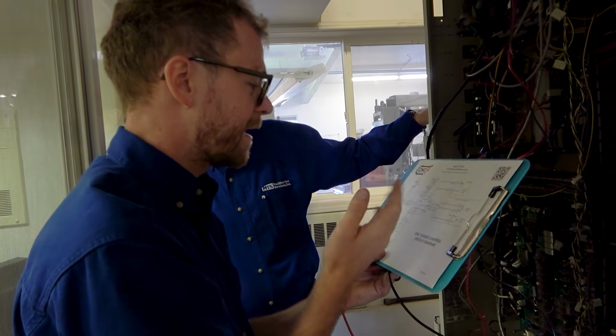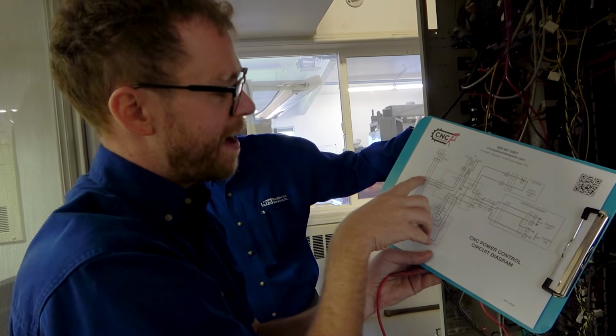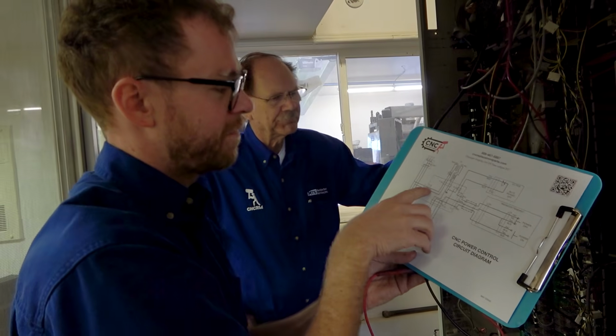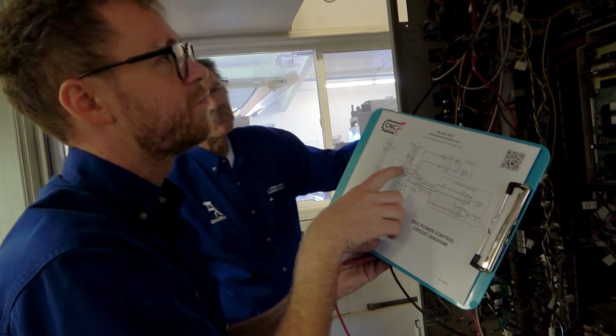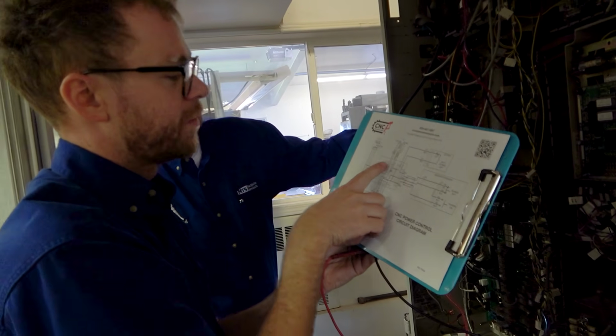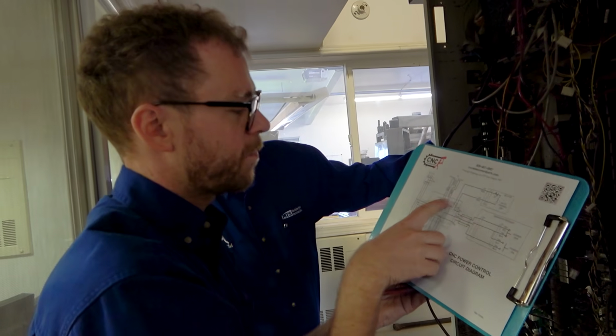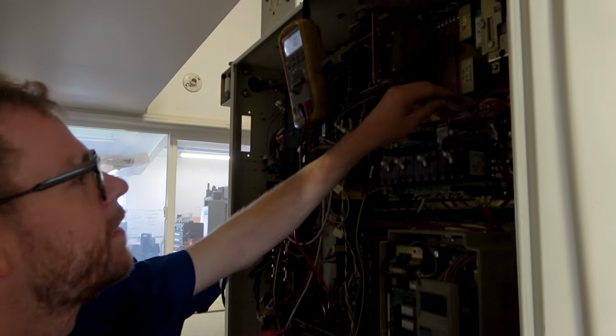In our case, we know the power gets to here at P25, and it then leaves to P24 and goes to the transformers. So let's check the power going to the transformers and the power coming off the transformers. So that's going to be P24, and if we look right here, and you got to be a little careful because we have live voltage up here. Here is P24. No. Let's see what we got here. This one and that one. These are not always labeled correctly.